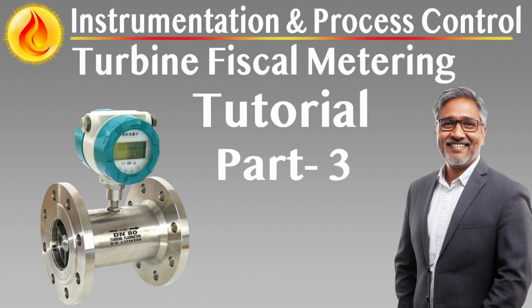Pulse generation and signal integrity. Each turbine meter must be fitted with dual magnetic pickup coils and signal preamplifiers. These dual pickups provide redundancy and allow pulse integrity checks through real-time comparison of signal trains. The design must permit removal and replacement of the pickup coils without removing the meter body from the line. Connections must allow for tamper-resistant sealing in accordance with regulatory requirements. Pulse outputs must be clean, distortion-free, and compatible with downstream microcomputer pulse input thresholds. Shielded cabling and signal isolation techniques must be used to prevent false triggering from electrical noise or grounding errors.